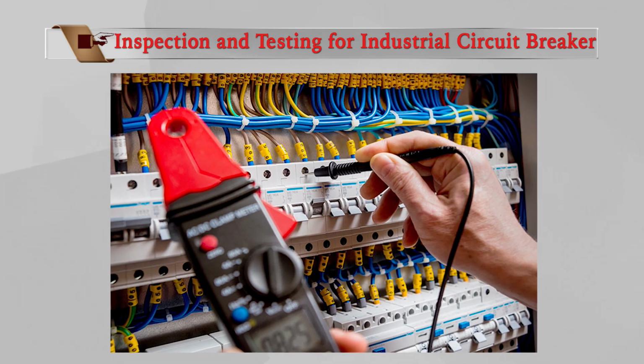Safety is the number one concern during repairs and maintenance of an electrical circuit breaker, to help prevent any issue or problem that may occur. All personnel should always wear personal protective equipment when working with the industrial circuit breaker. There are also industrial circuit breaker locks that help to lock the circuit breaker while it is being serviced so that it does not accidentally close in the middle of the process. Special care and precautions should always be taken because of the high level of risk involved in working with the industrial circuit breaker. Now we are going to discuss inspection and testing for the industrial circuit breaker.